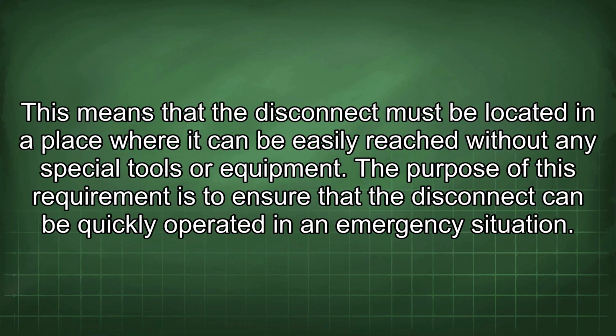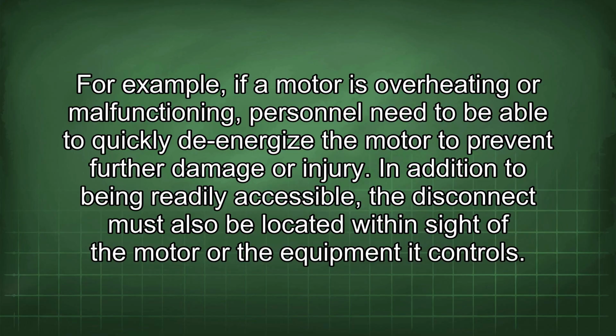This means that the disconnect must be located in a place where it can be easily reached without any special tools or equipment. The purpose of this requirement is to ensure that the disconnect can be quickly operated in an emergency situation. For example, if a motor is overheating or malfunctioning, personnel need to be able to quickly de-energize the motor to prevent further damage or injury.